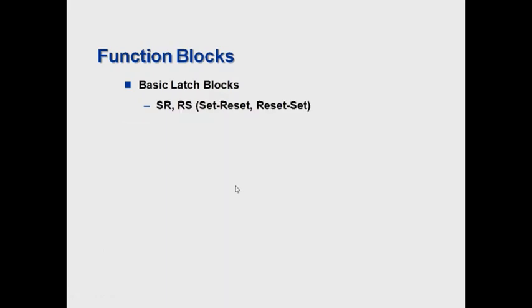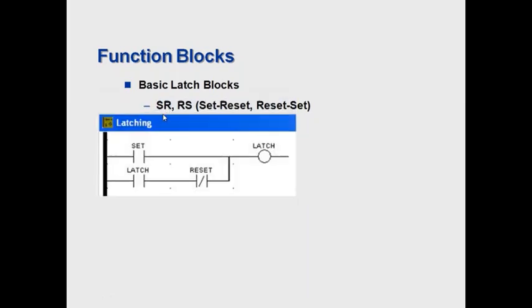Some basic latch blocks are SR, or set reset, and RS, or reset set, which means in SR, the set is dominant. So if S and R are both set, for example, in this ladder diagram, we'll notice that if the set and the reset are both energized, our set still is the dominant input and will leave the latch or output energized.